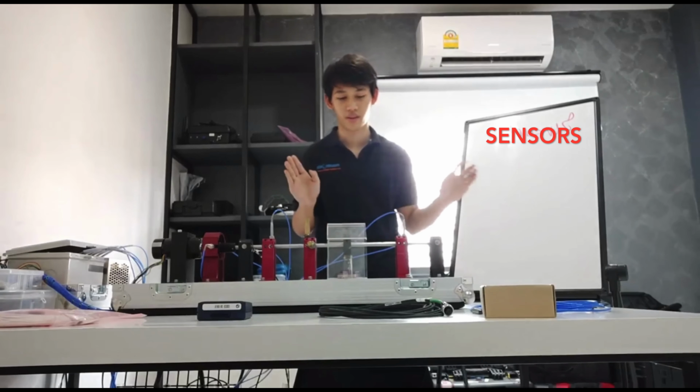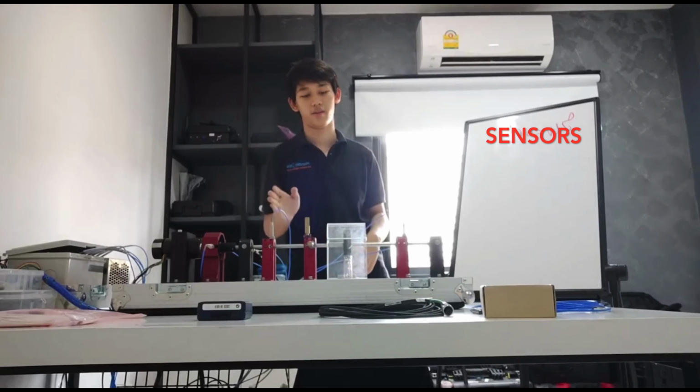It is quite advantageous, first because it is non-contact. This means that when the mechanical part vibrates too hard, or when another factor makes the axle or the machine vibrate really hard, it cannot affect the displacement sensor because it doesn't touch the axle or the machine. So it is safer than the acceleration sensor, or you can call it an accelerometer.